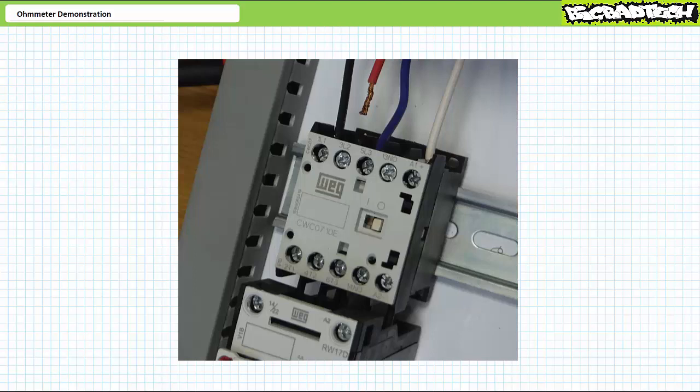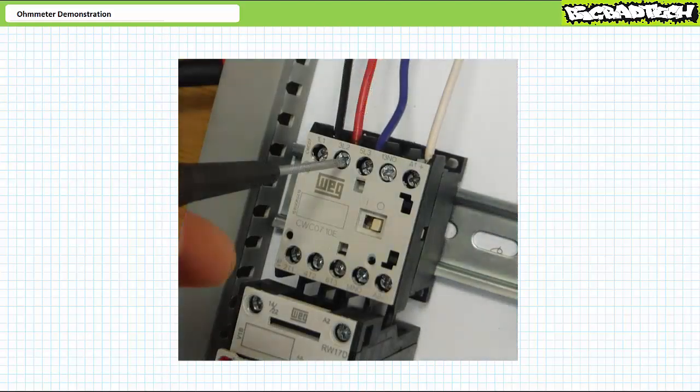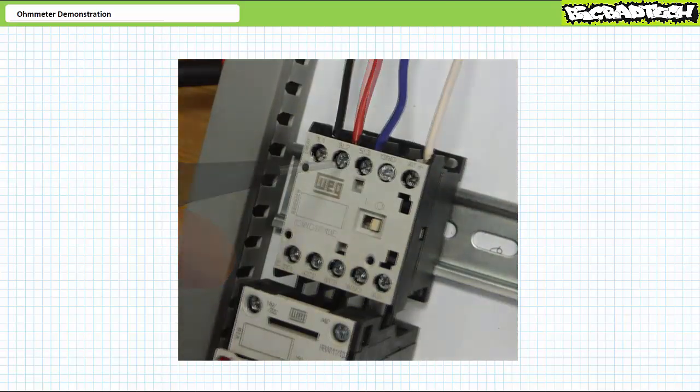Even if you don't know what three-phase AC is, nor how ladder logic governs the operational state of this contactor and the motor under its direction, just look at it. It's immediately evident there is a loss of connection. Lock it out, tag it out, tighten it up, and return it to service. Problem solved.